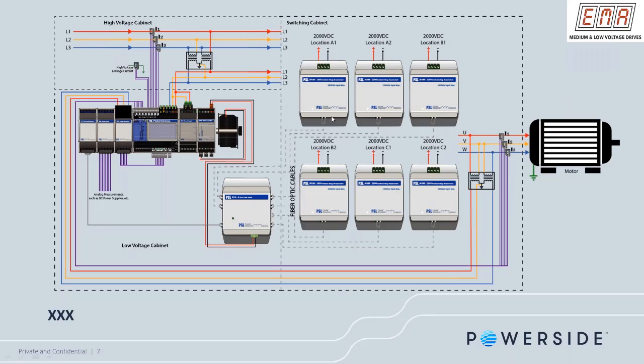so the interface between the MVM modules and the fiber optic interface module is through fiber optic isolation, right? So therefore, we would not bring any interference between the medium voltage and the low voltage, and also safety, because if you have electrical wires, you could potentially, if there's a failure on the medium voltage section, introduce that medium voltage into low voltage, and we don't want to do that. So that's why we isolated with fiber optic cables.